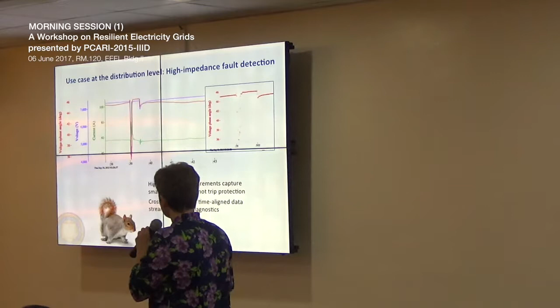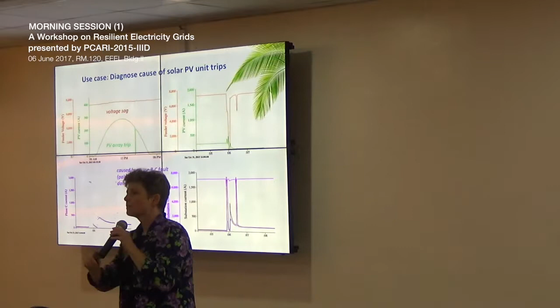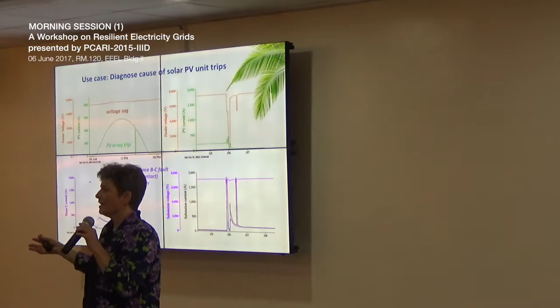There's also a use case for local solar PV plants tripping offline. Sometimes there's finger pointing: your inverter wasn't behaving well, versus we tripped offline because your utility system gave us weird power quality and we're supposed to disconnect per our interconnection agreement. So who's right? We can see exactly what happened. In an example from Southern California, the big inverter that seemed to behave badly was actually behaving as it was supposed to, it was a palm tree causing a fault that produced just enough voltage sag to trip the inverter.